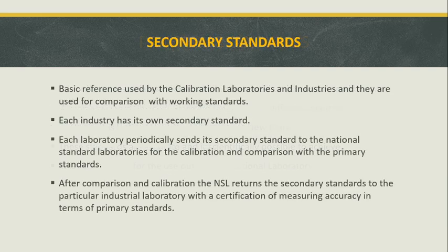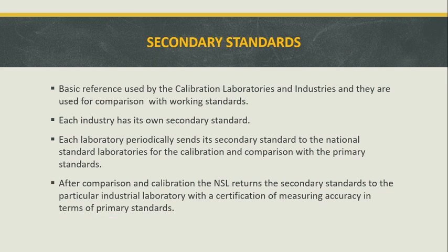And next one is secondary standards. These standards are the basic reference for the calibration laboratories and industries. They are used for comparison with the working standards. Each industry has its own secondary standard. For each and every industry, they can produce their own secondary standards.